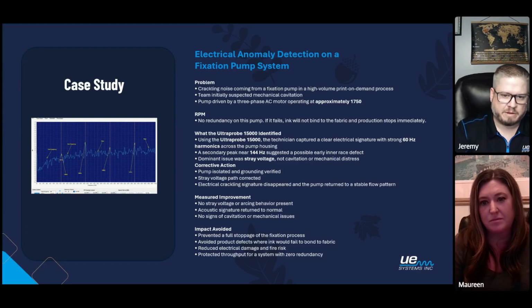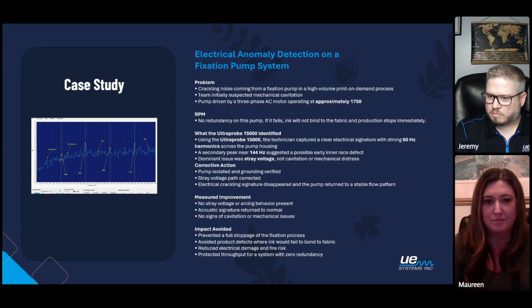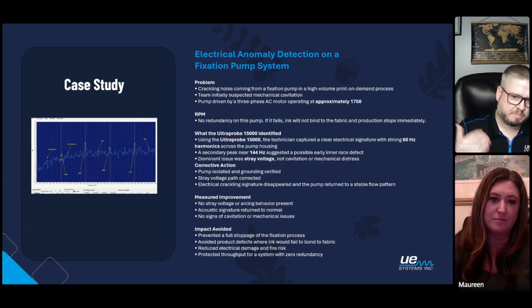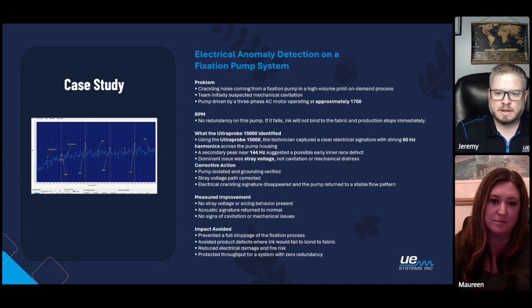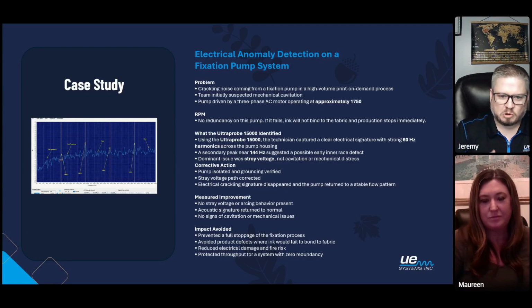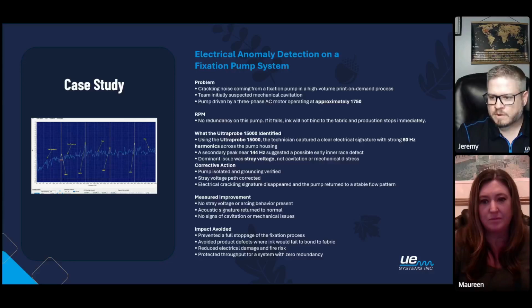So the team was going out and they were doing their normal inspections. They do a visual inspection, and they heard a crackling noise at this pump. So the first thought: it's a pump, it's got to be cavitation. So they went out with the ultra probe, though. First, they messed with their pressures and whatnot, trying to get that cavitation out of there. Didn't work. Took the ultra probe out. We're able to take some readings. We're actually able to analyze the harmonics.